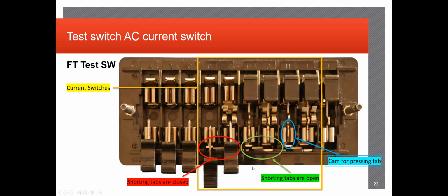So yep, shorting tabs, you can identify them if they're closed or open too. Another thing you want to watch out for as well is that for testing purposes, sometimes you actually want the CT circuit to be open. And the only reason I say that is because the circuit should be powered down and all you're doing is verifying wiring checks to make sure that everything is correctly laid out based on the prints or whatnot.